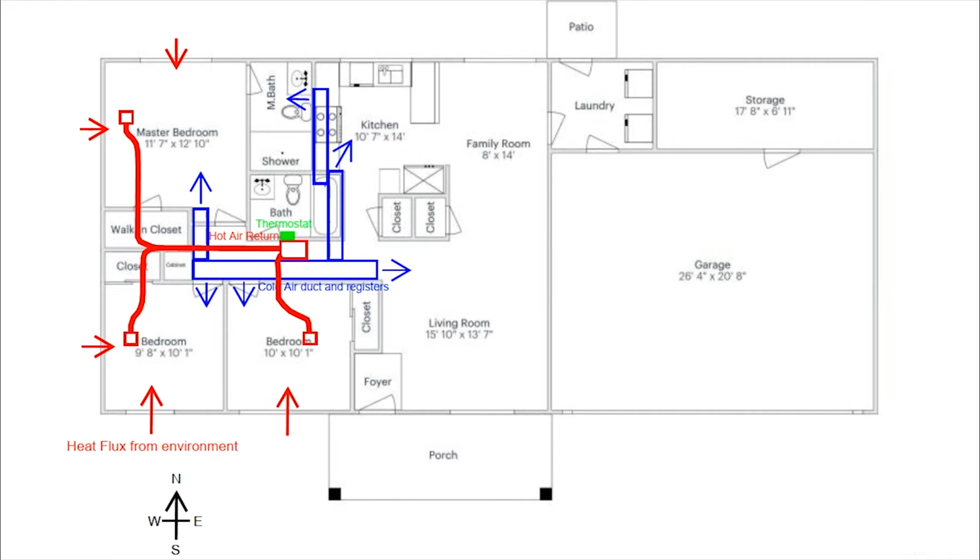So for the registers on these new hot air returns, I used register boots to have a 6-inch duct connection, and I used a 6-inch flexi duct with the thicker higher-end insulation options from each of these bedroom returns to the main return.